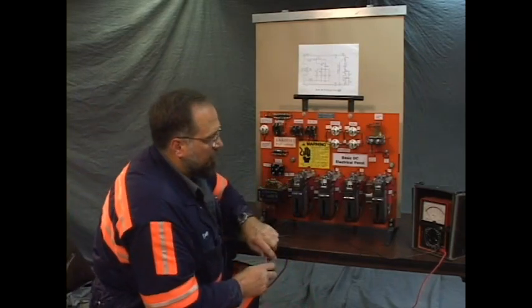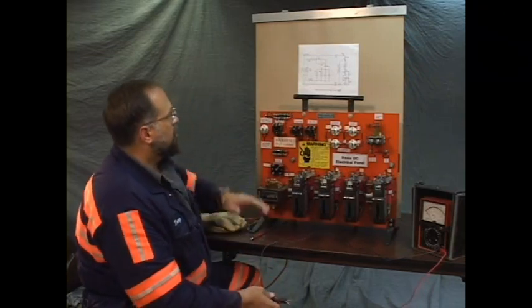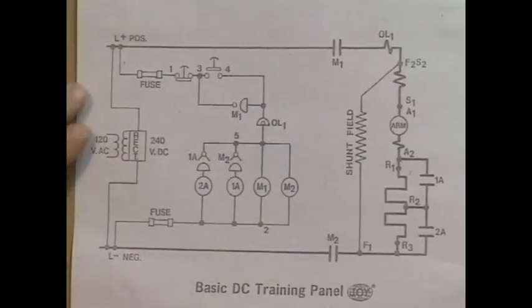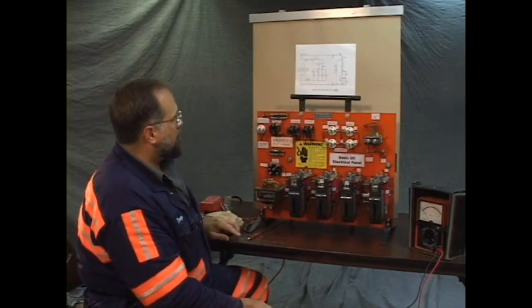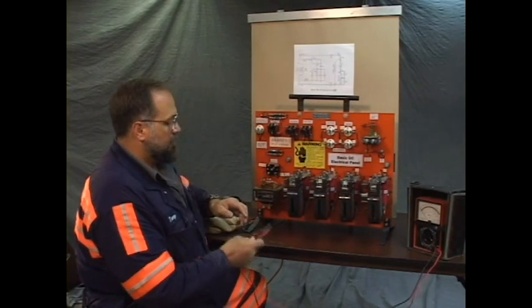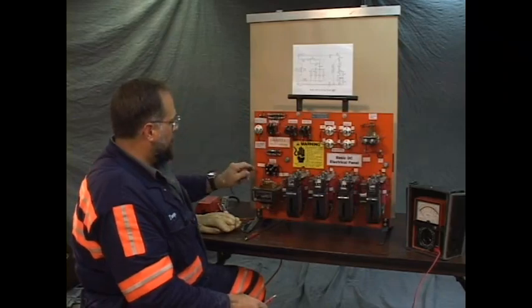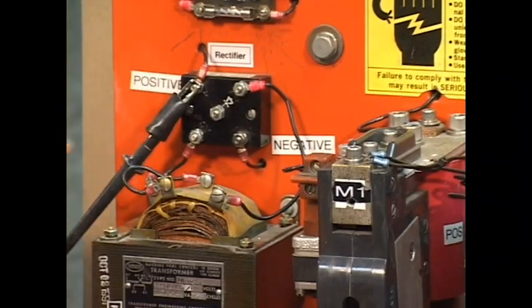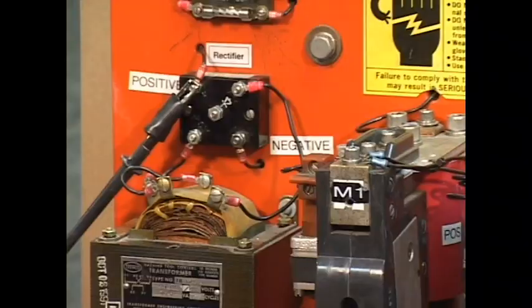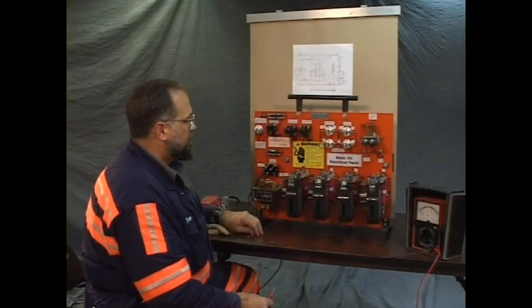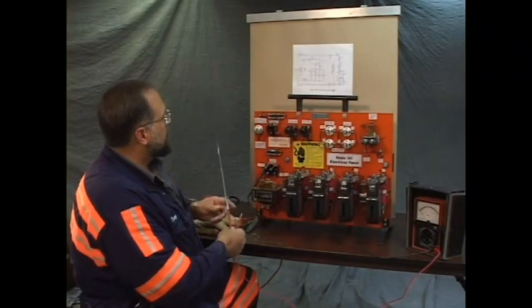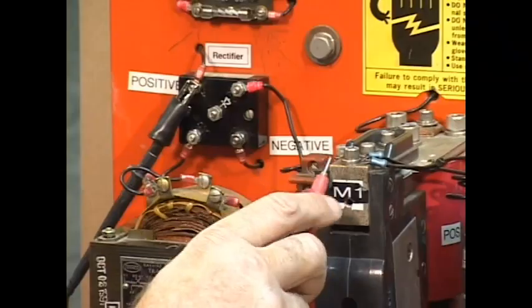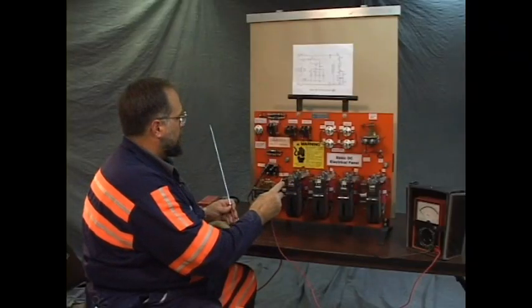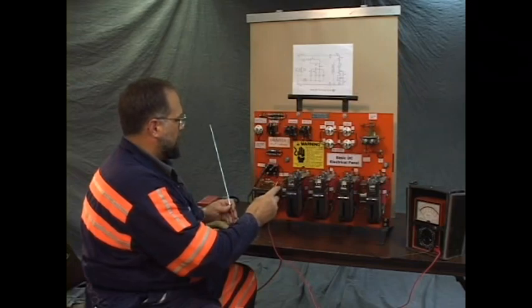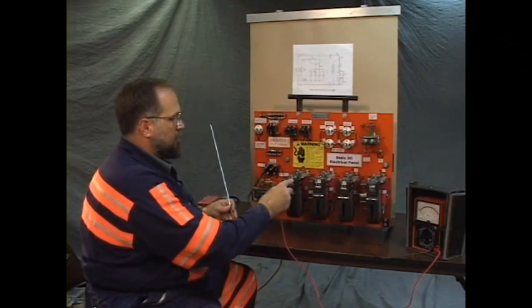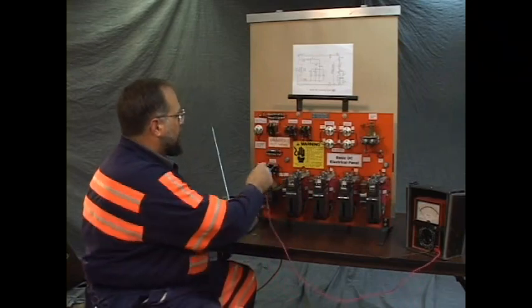With nothing operating, nothing on the circuit works, you don't know, it could be any part of the control. Nothing works. So we'll start at the beginning, which is always a good place to start. I'm going to attach one of my meter leads to the positive of the rectifier, and I'm going to proceed in a line-by-line fashion until we find our problem. On my first test, I don't have a problem. Let's check our meter.